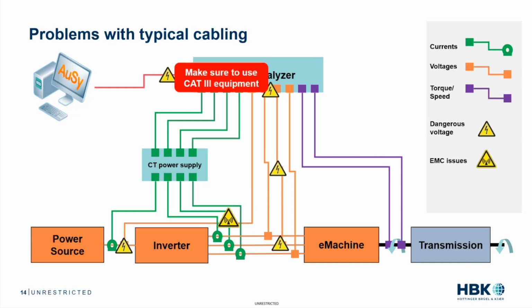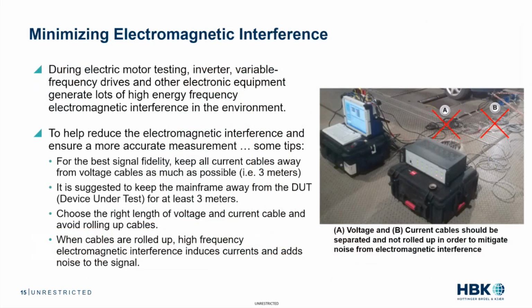So you've got EMC issues, of course, throughout the measurement chain. So quite a few things to be concerned about, whether it's the cabling, the sensors, the method in which you connect things to your power analyzer and so forth. And so let's talk about some of these things and how to mitigate some of these issues. Basically, during an electric motor test, you've got the inverter, variable frequency drives, and other electronic equipment generating high energy frequency, which we call EMI, electromagnetic interference. To help reduce the electromagnetic interference and ensure more accurate measurements, for the best signal fidelity, you want to be sure and keep all the current cables away from voltage cables as much as possible. One suggestion is 3 meters. And it's suggested to keep the mainframe, the power analyzer, away from the device under test by at least 3 meters as well. You want to be sure and choose the right length of voltage and current cable, because you want to avoid rolling up the cables.